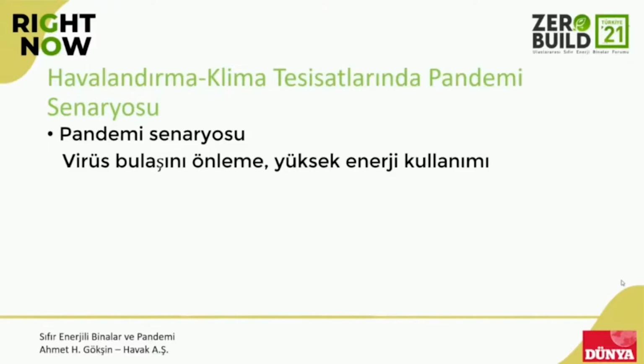However, when we are in 100% fresh air, the heating and cooling capacities will not be enough, and therefore these capacities should be increased, and this means more energy consumption. If we cannot have it, we can use recycled air, and this air should go through HEPA filters so that we can catch the viruses. When we use HEPA filters, there is additional resistance, and the current fans cannot cover that. It's about increasing the power of a fan, or an additional fan could be included, so it requires additional energy consumption.